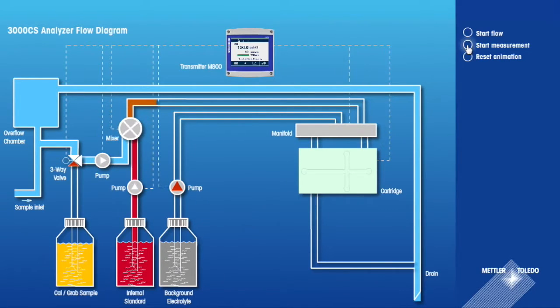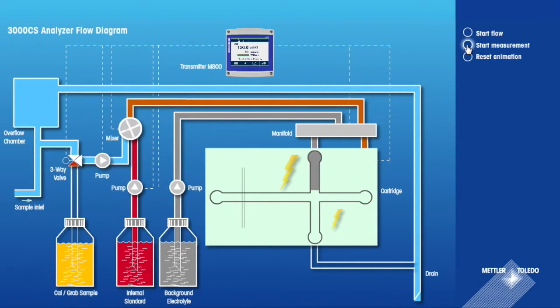At the start of each measurement cycle, a fresh water sample is loaded, along with associated electrolytes and standards, onto a cartridge in the unit. The analyzer separates ions based on their mobility by applying a high voltage in a small capillary on the cartridge.